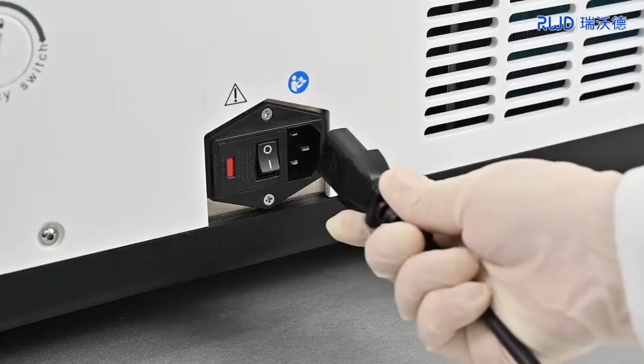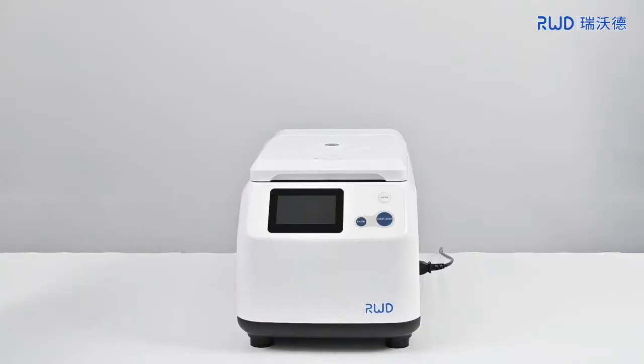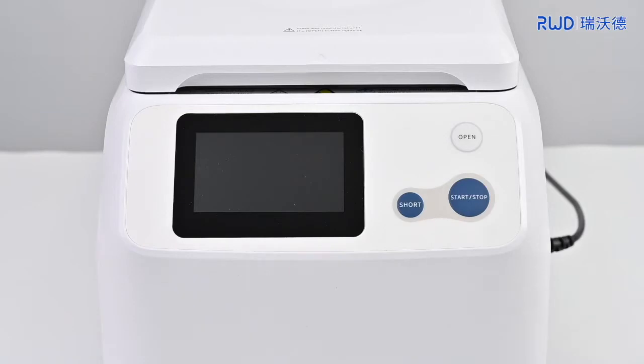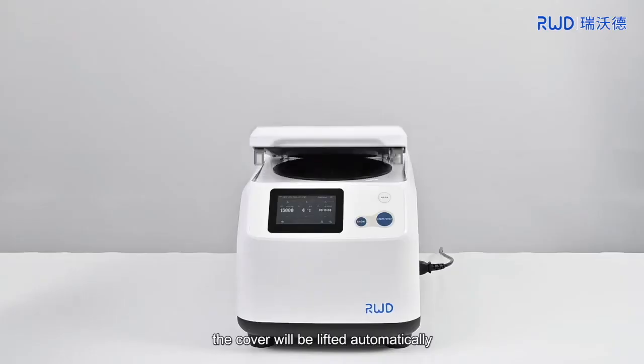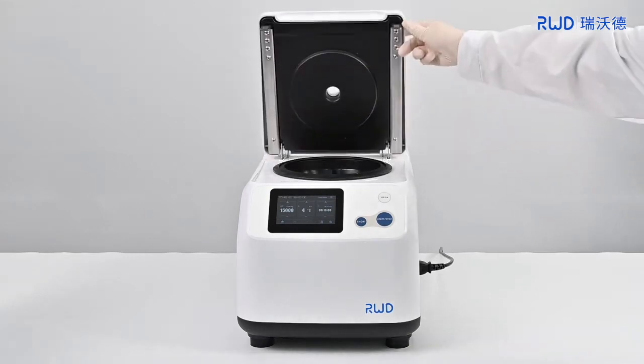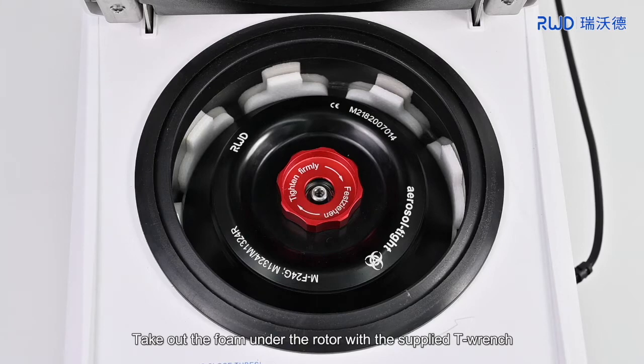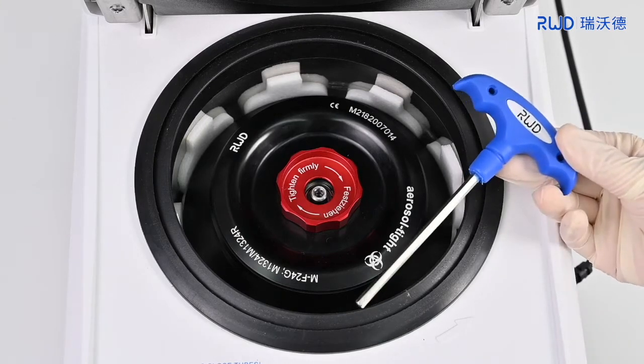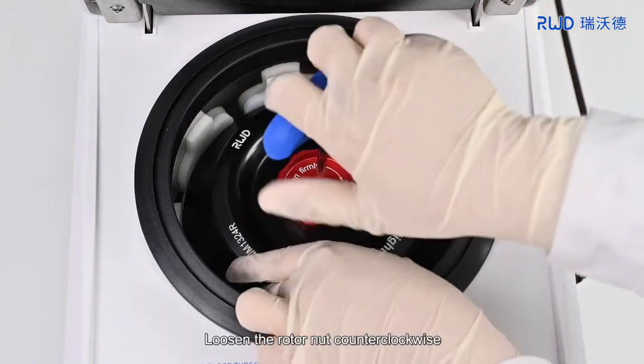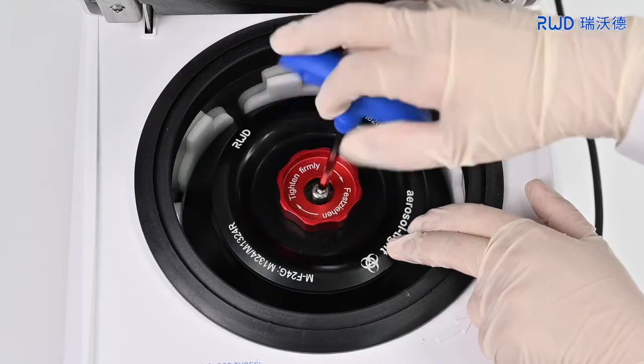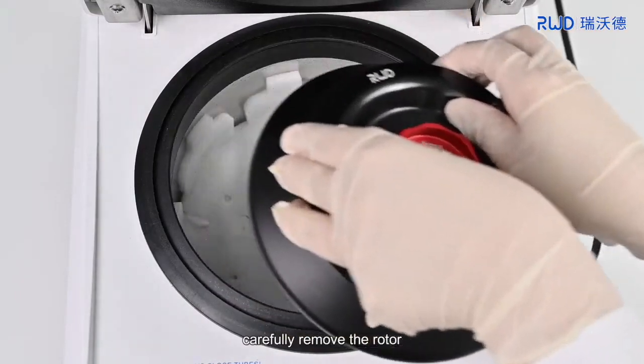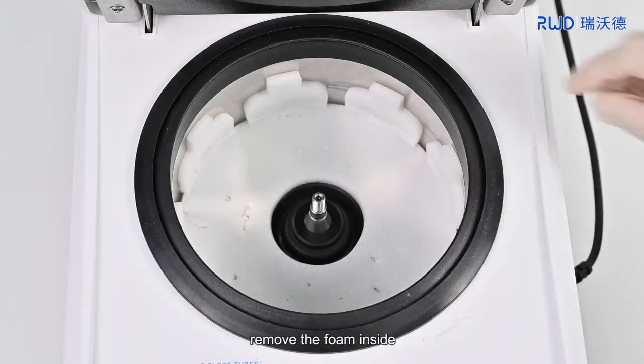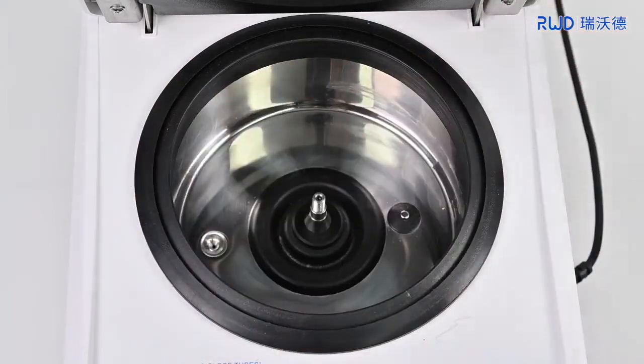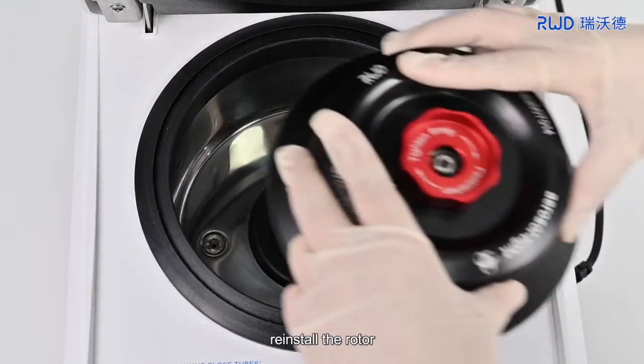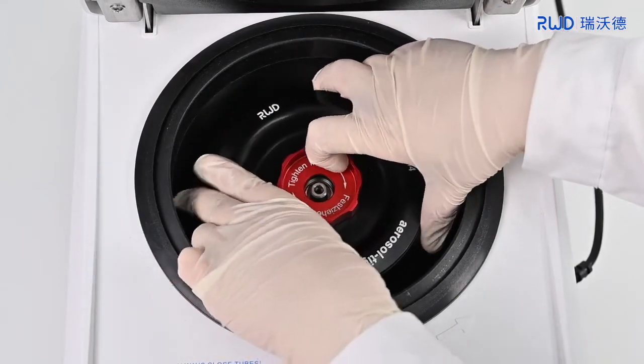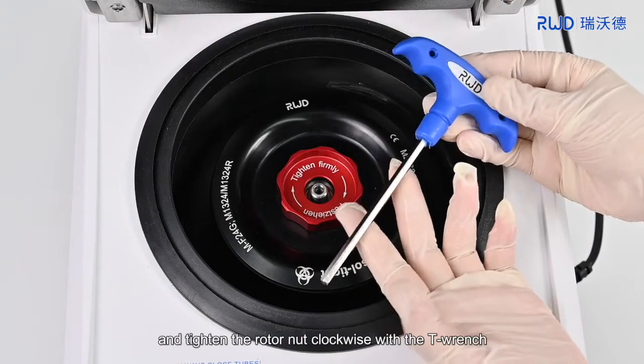Connect the power cord. After starting the machine, the cover will be lifted automatically. Take out the foam under the rotor with the supplied T-wrench. Loosen the rotor nut counterclockwise. Carefully remove the rotor. Remove the foam inside. Reinstall the rotor, and tighten the rotor nut clockwise with the T-wrench.